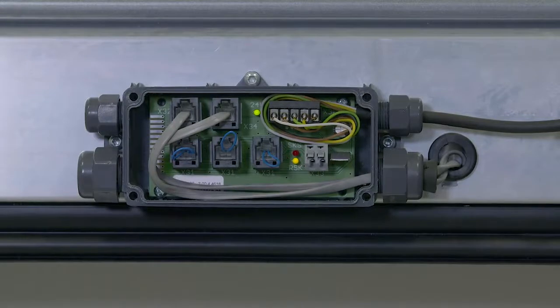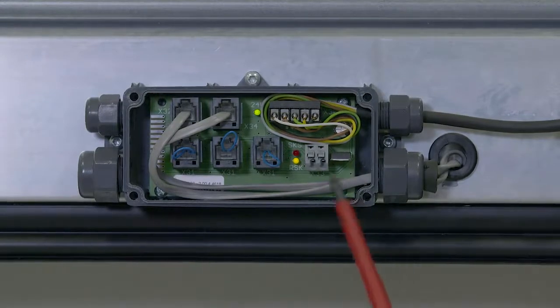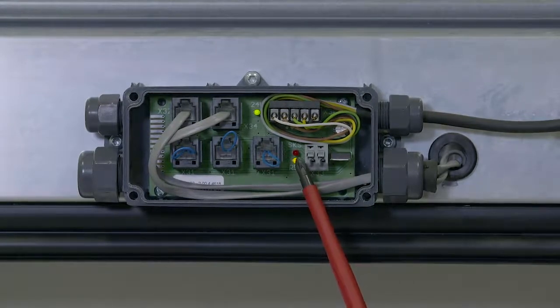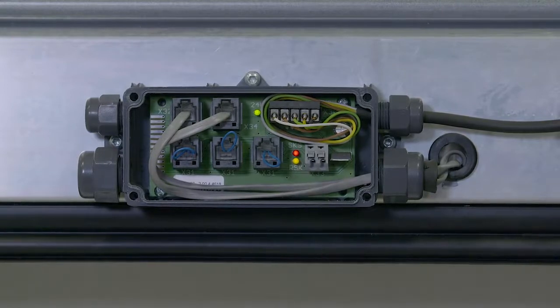We can check the LEDs in the SafeEdge PCB to see if the red SKS light is illuminated. If it is, the optics aren't seeing each other. Check for damage.